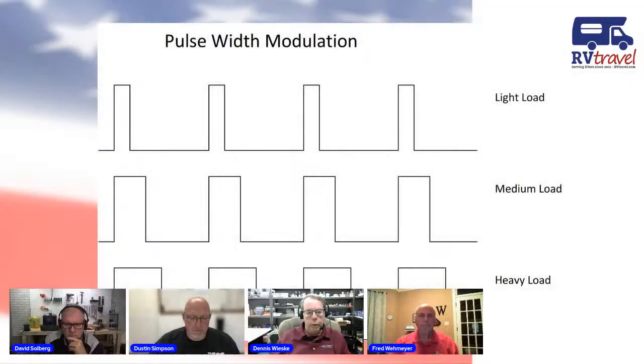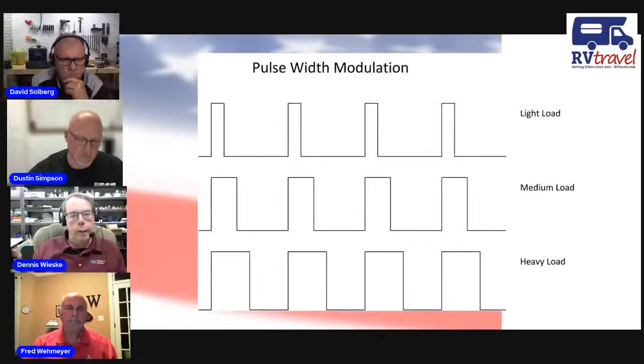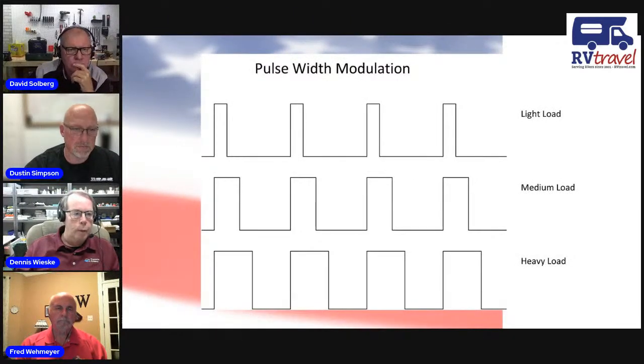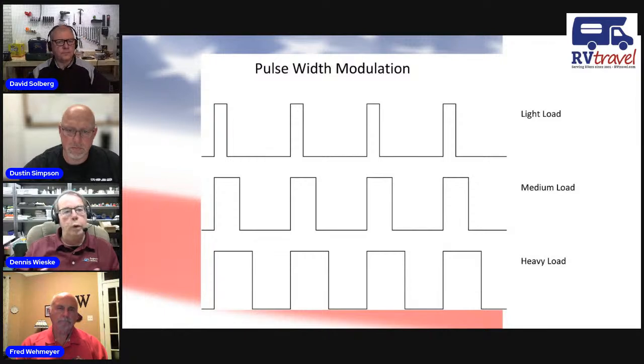The whole principle of this operation is to maintain a fixed voltage on the output of the charger. You don't want the load to change and the voltage to drop off, or the load to be lightened and the voltage to go sky high. If you increase the load, as in the center picture with a medium load, you'll notice the pulse width increased, because we were trying to feed a heavier load, putting more power out through the transformer.